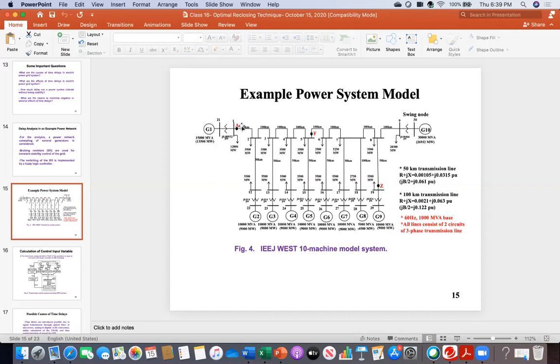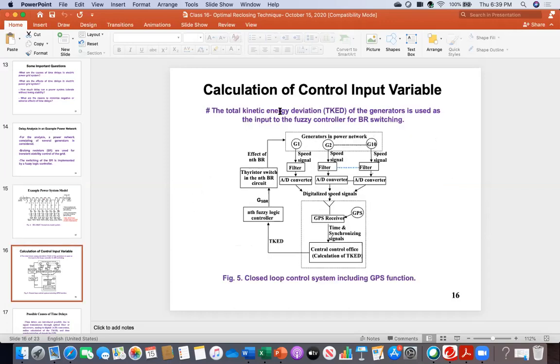So you put a braking resistor at the terminal to maintain transient stability. You know the process of how the braking resistor works - our talk is about the controller. That braking resistor controller needs total kinetic energy information, which is why you see G1, G2, G3 - there are 10 generators, and from all of them it collects this data. Here I've shown the calculation of the control input variable, assuming the fuzzy logic controller is here.